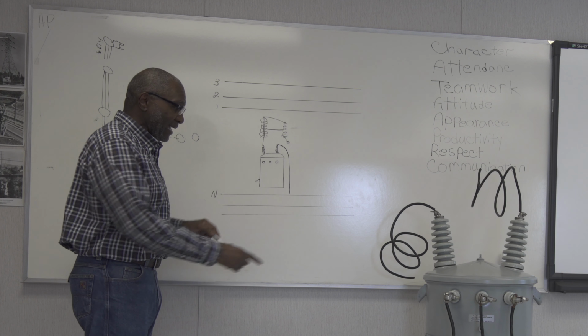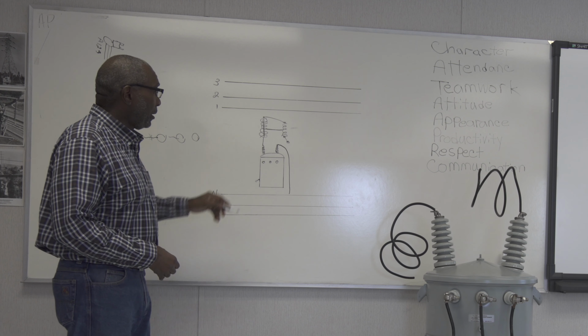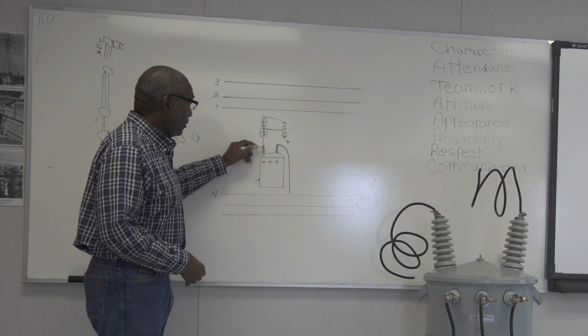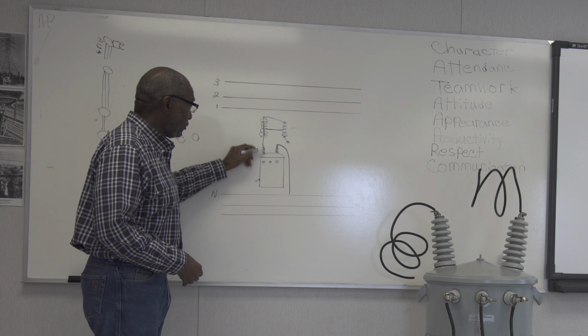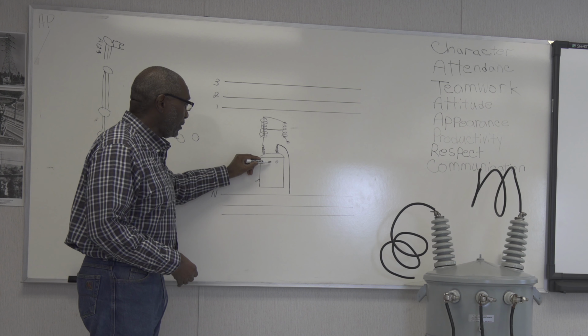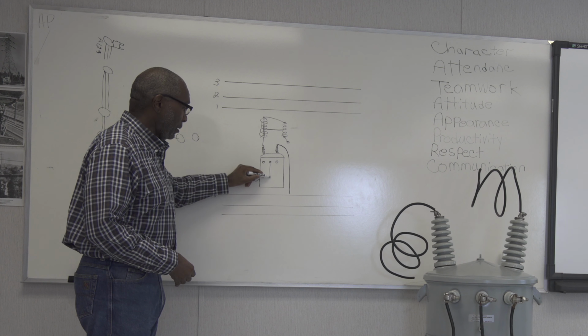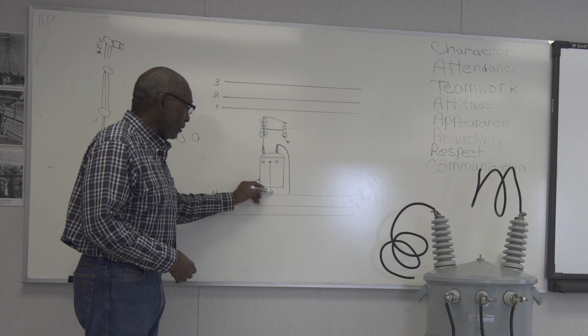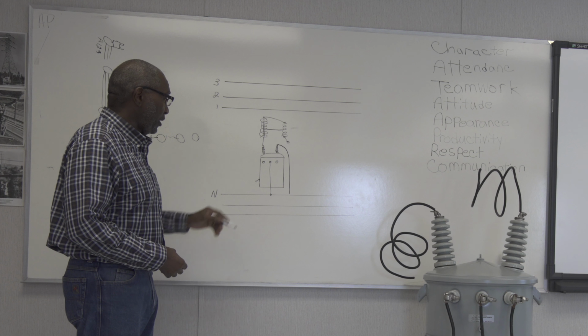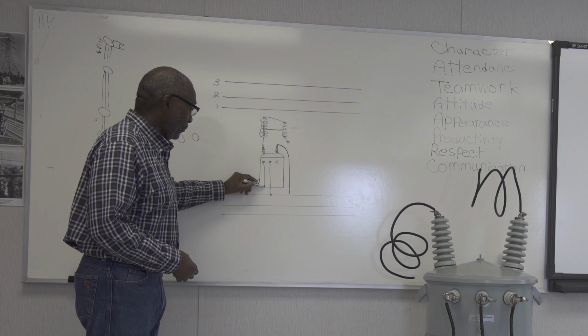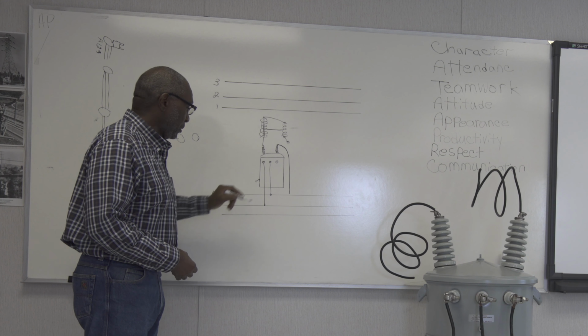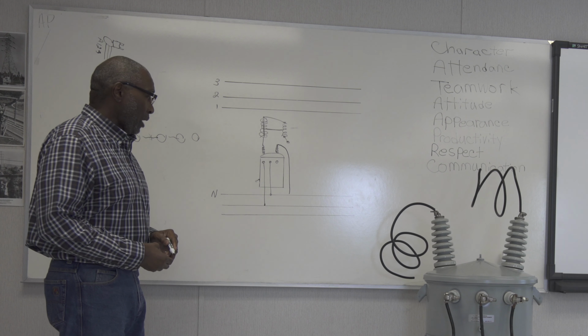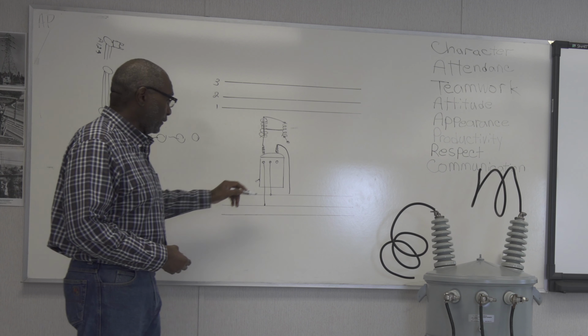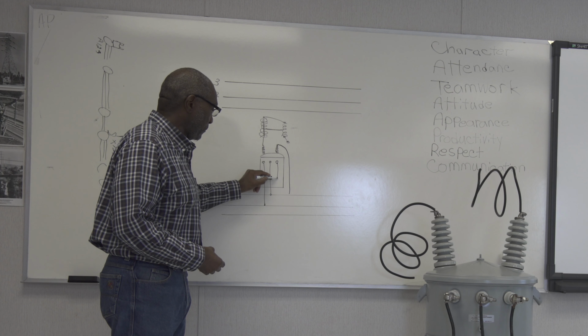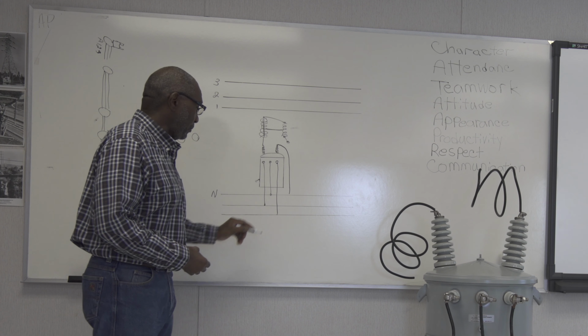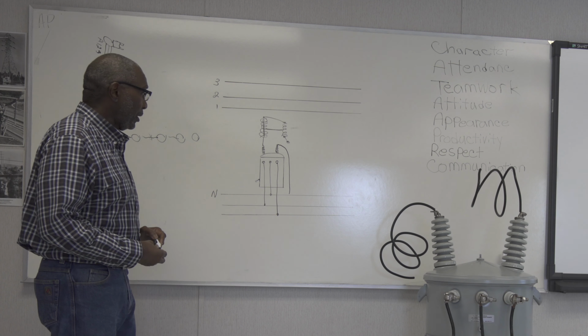This is the neutral, this is hot leg on your low side, secondary side of the transformer. After going through the windings as I demonstrated there, you come out, 7200 volts in here, coming out 120 volts. You're going to make your hookup on your neutral there. Bring the other one to your hot leg out of your service. And the other one will go here.